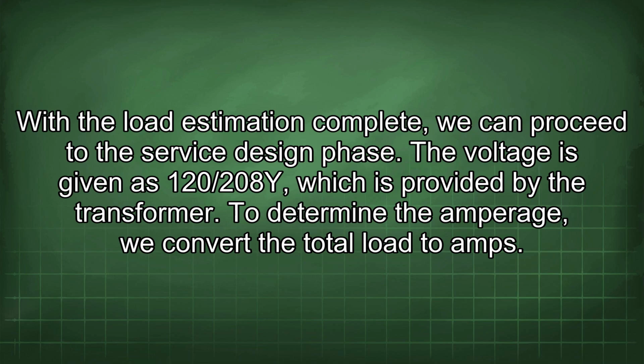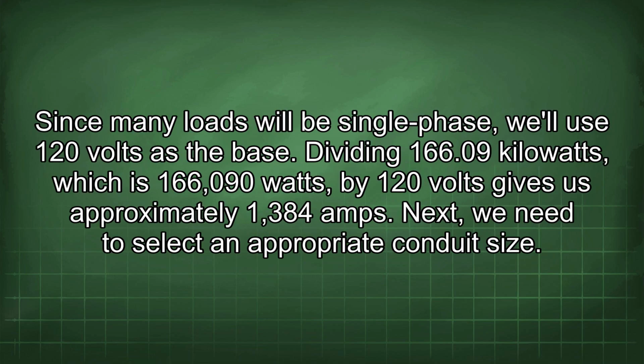The voltage is given as 120/208Y, which is provided by the transformer. To determine the amperage, we convert the total load to amps. Since many loads will be single phase, we'll use 120 volts as the base. Dividing 166.09 kilowatts, which is 166,090 watts, by 120 volts gives us approximately 1384 amps.